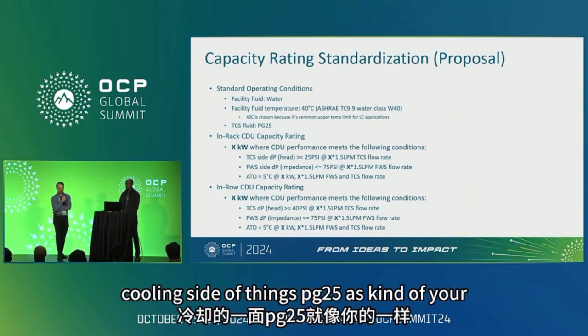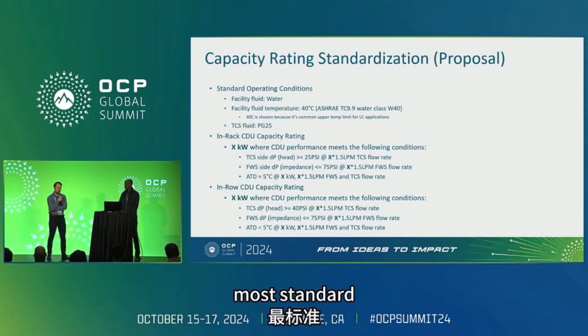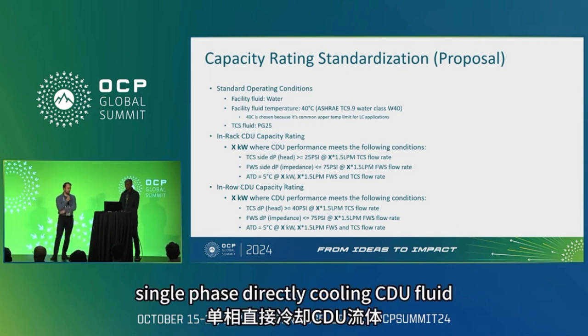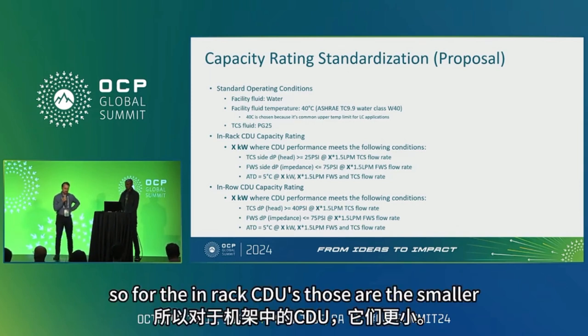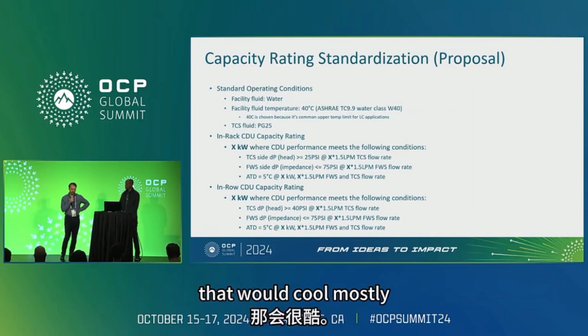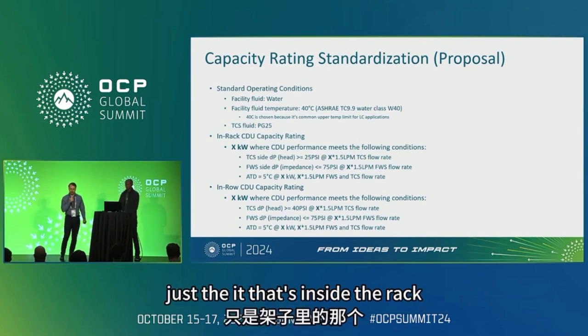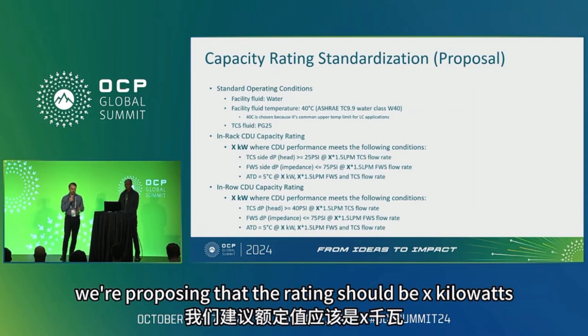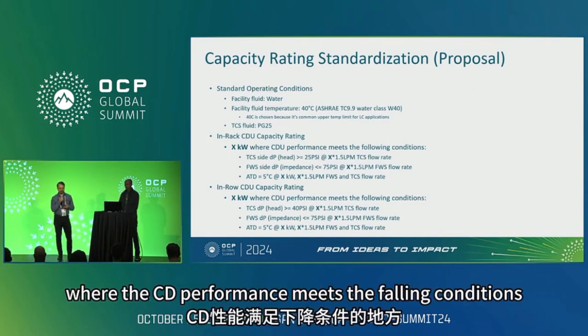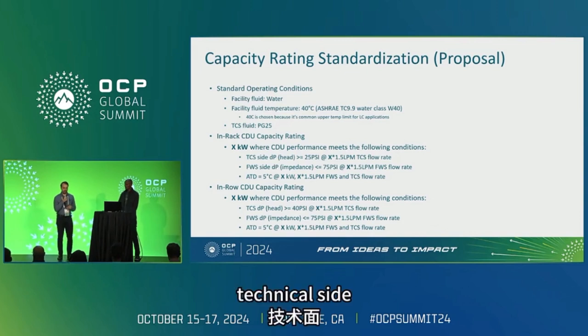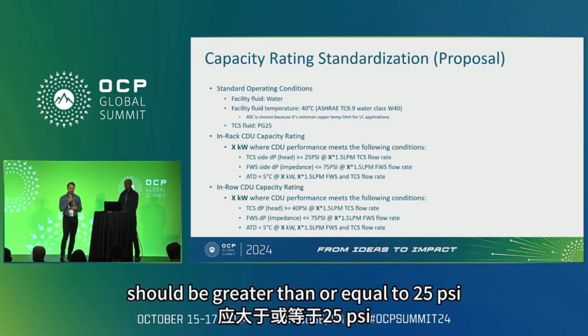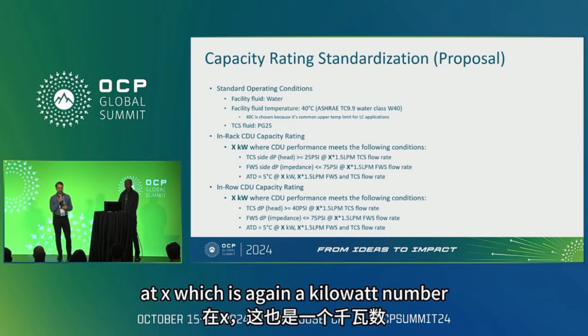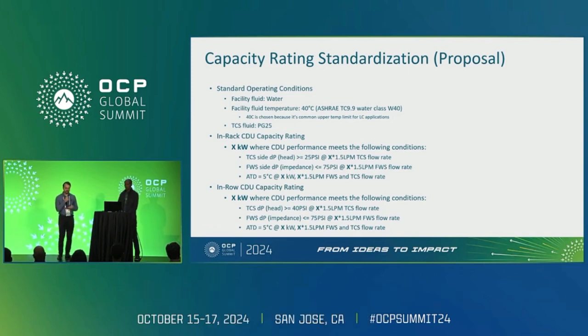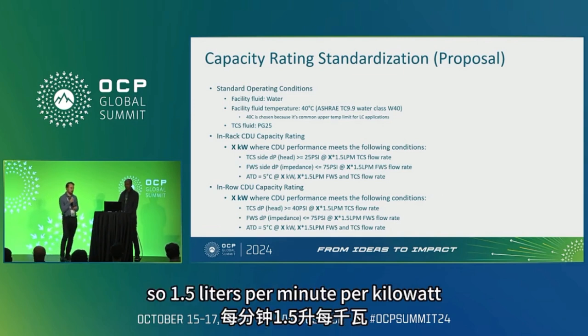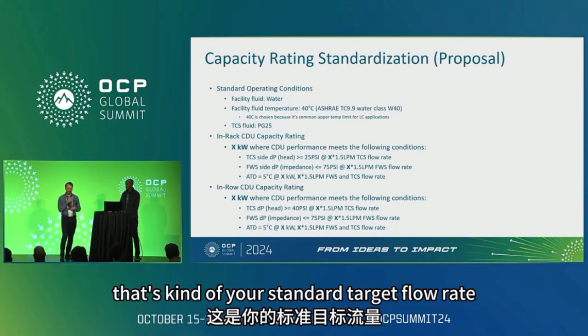And on the technical cooling side of things, PG25 as kind of your most standard single phase direct liquid cooling CDU fluid. So for the in-rack CDUs, those are the smaller systems that sit inside the rack that would cool mostly just the IT that's inside the rack. We're proposing that the rating should be X kilowatts, where the CDU performance meets the following conditions. Technical side, DP pressure head should be greater than or equal to 25 psi at X, which is again a kilowatt number, times 1.5 liters per minute. So 1.5 liter per minute per kilowatt as kind of your standard target flow rate.